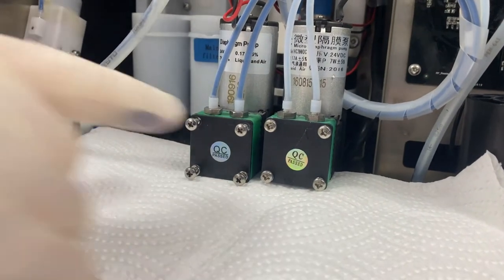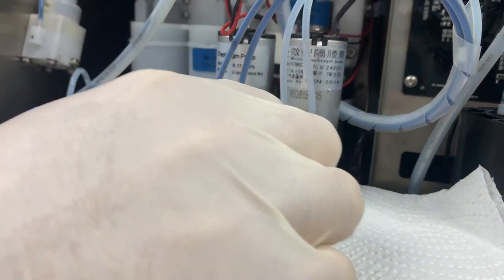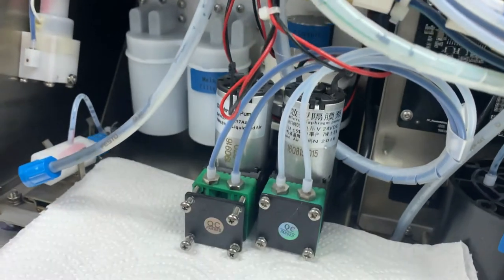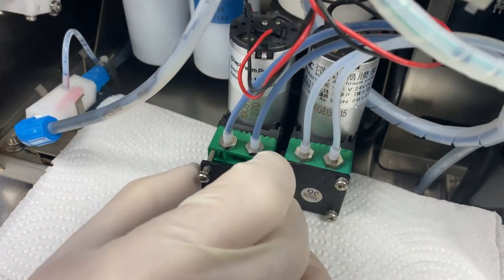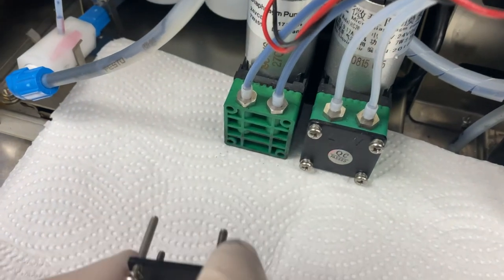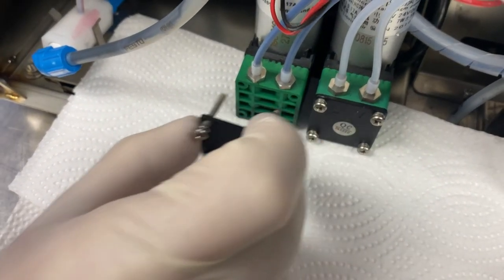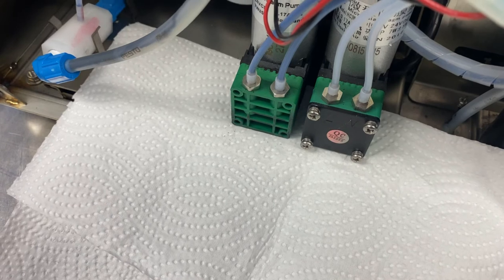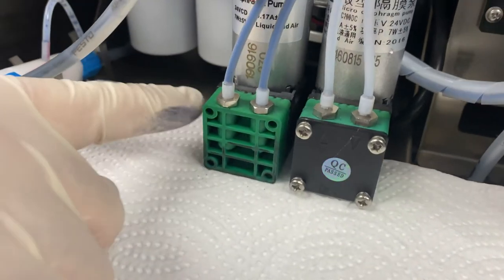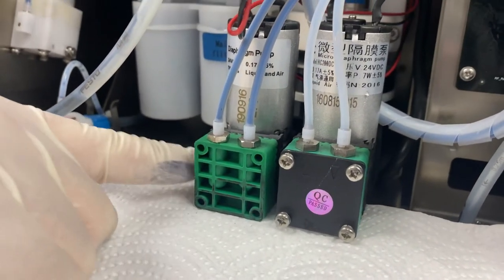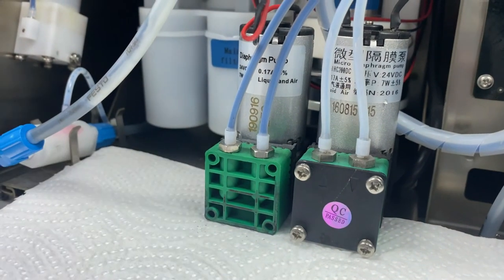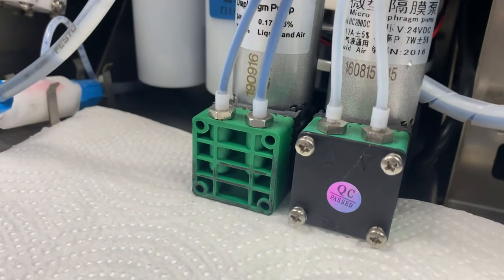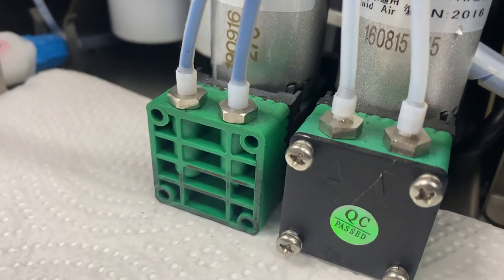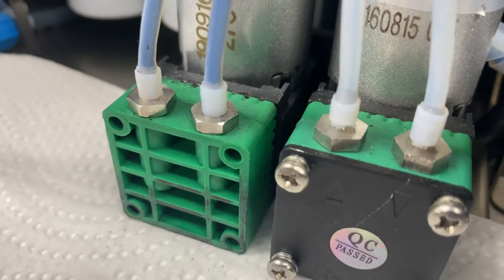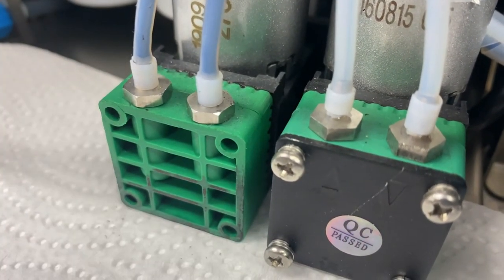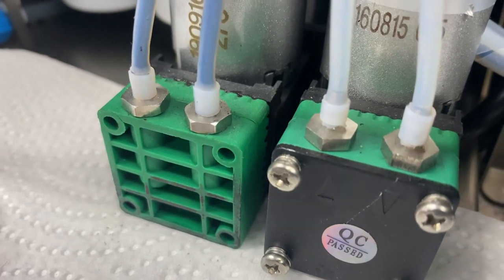Okay, so we've got our four screws loosened up so we can start pulling this assembly apart. You'll see there's this black cap that goes over the top of everything. We're sliding that out, and now there are two main pieces here, two green blocks. In between these blocks, we have an input and output flap that open and close when the diaphragm is moving in and out. So we're gonna take this apart and take a look at those to make sure they're not stuck.